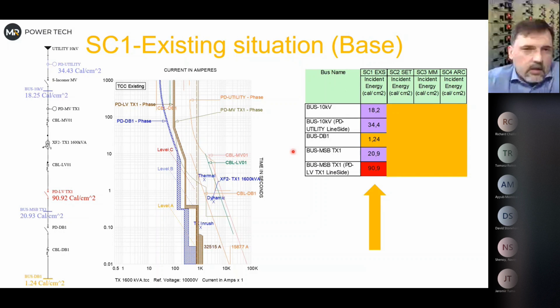Again, we have the existing situation, just to give you a reference point, we have a base. I use this to show your results, and you might see a time current curve. This is a graphical way of showing protective device settings between medium and low voltage. At the utility we don't have data, so it will stay like this, 34 calories. We have a 10 kV bus, 18 calories. We have a low voltage breaker, which is now 90 calories because of the incoming side.